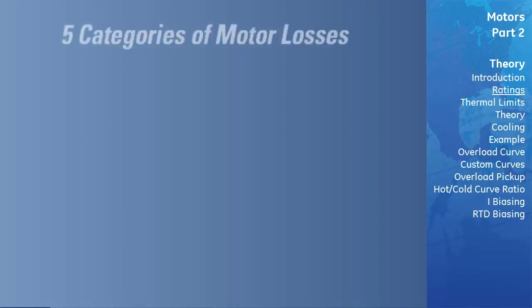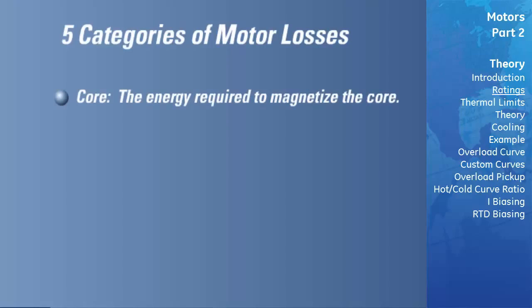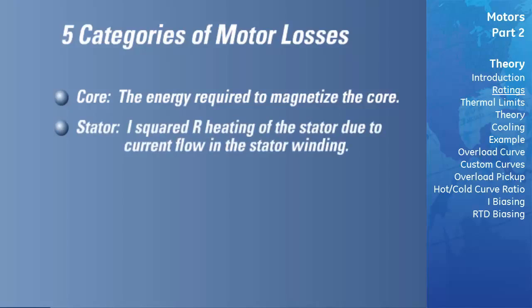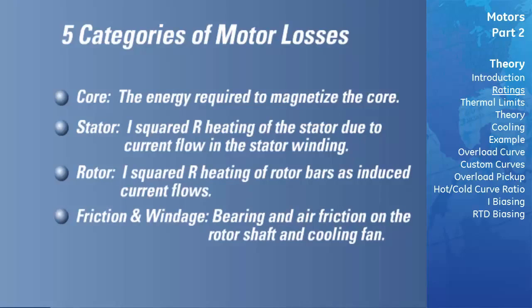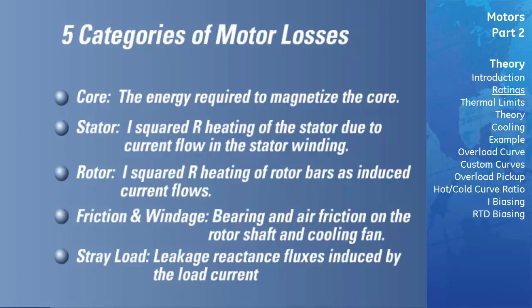There are five categories of motor losses. Core losses are comprised of two components: the energy required to magnetize the core and eddy current losses in the stator core. Stator losses are due to the I-squared R heating of the stator due to current flow in the stator windings. Rotor losses are due to the I-squared R heating of rotor bars as induced current flows. Friction and windage losses are due to bearing and air friction. Stray load losses are due primarily to leakage reactance fluxes induced by the load current. Core, stator, and rotor losses typically make up greater than 80% of the total motor losses.